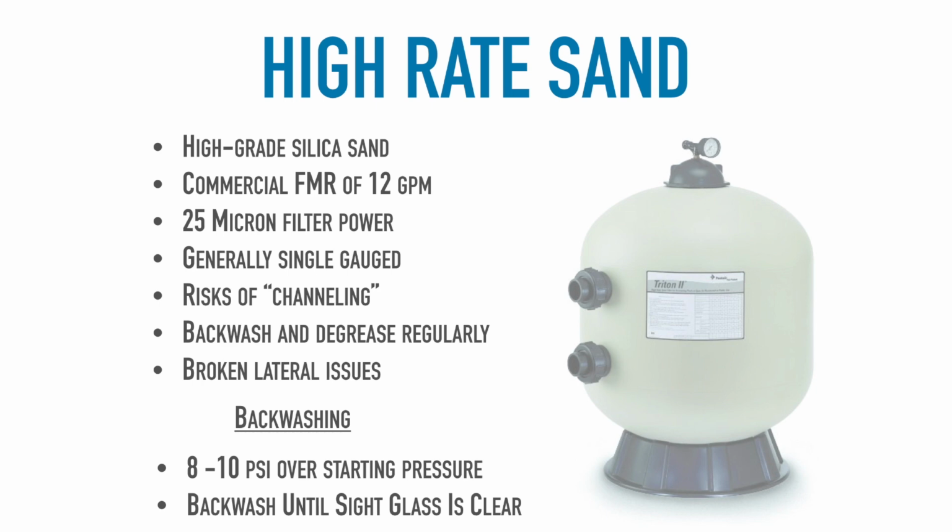Once you're done replacing them, you're going to fill that filter about halfway up with water and then start slowly pouring the bags of sand inside of that filter. Make sure that you're not dumping it down in there, because if you dump it down in there, it's going to land on those laterals and it could break those laterals and end you back up at square one again.